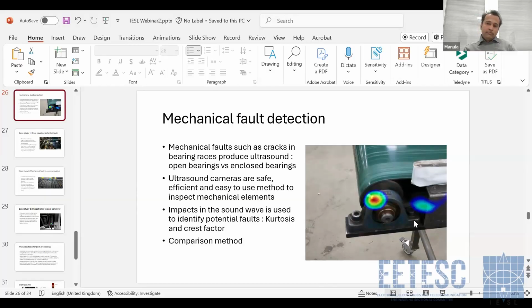You can't exactly say whether it is from the housing or the bearing inner race or outer race, because you can't have that much spatial resolution with this kind of camera. That's why, as I said earlier as well, if you want this kind of detection, it is best to use comparison. There is another bearing on the other side, so you can get the SPL level, kurtosis and so on, and compare it with a similar bearing. That's the best way to detect faults for this kind of application, because this kind of noise can be normal as well. From one single detection, we can't exactly say whether it is a fault or not.